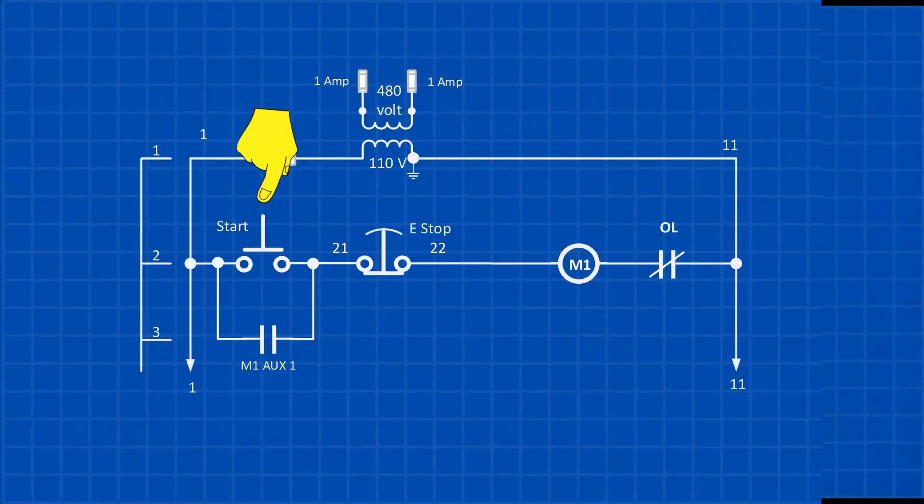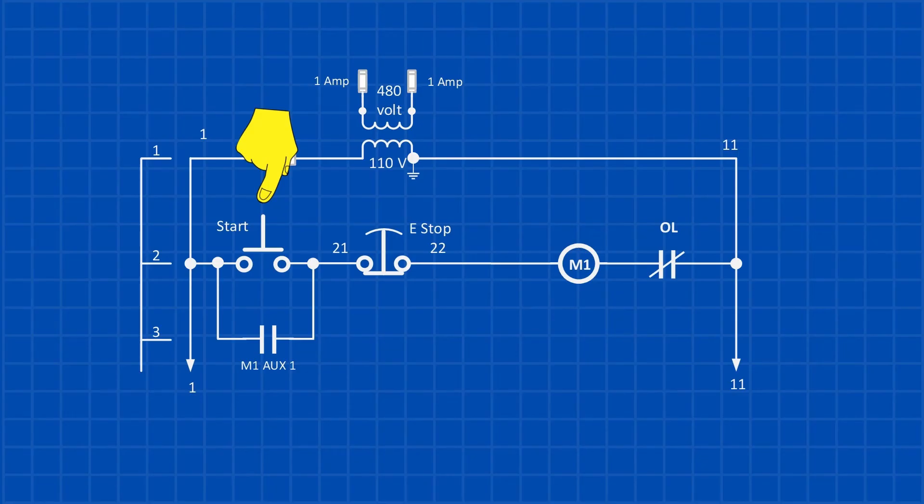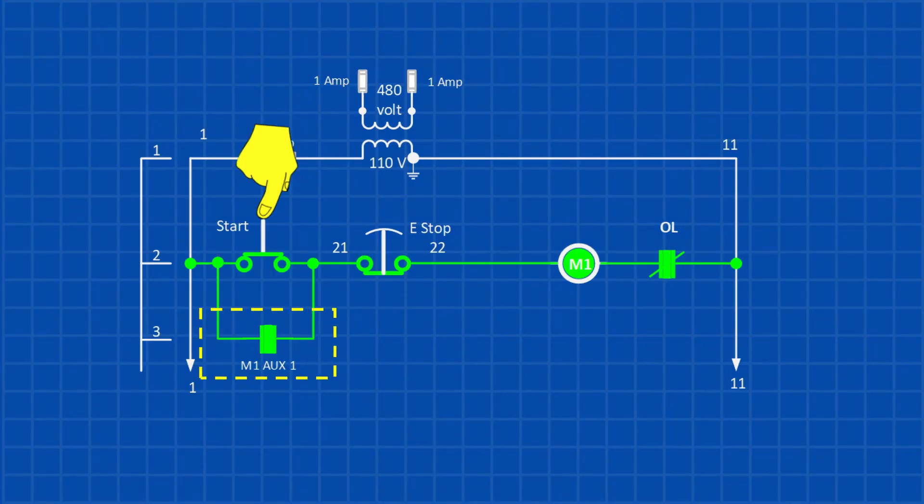A motor starter control circuit uses what's known as a latching circuit. A latching circuit keeps the motor starter energized even after the initial start signal is removed. It works by using one of the motor starter's normally open auxiliary contacts, which is wired in parallel with the start button. When you press the start button, it energizes the M1 coil, closing the auxiliary contact. This contact then continues to supply power to the coil even after you release the start button.